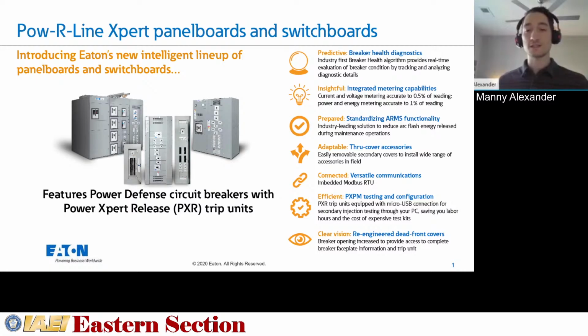All of the data that these breakers are collecting is incredible and great, but we want to be able to provide that data to a higher level system for action to be taken. Other things such as the ability to plug your computer via micro USB port into the trip unit gives you the ability to perform secondary injection testing on the breaker, pull all of that great breaker data, and perform test reports that can be compiled in PDF format. So just a lot of great things that you can pull from these breakers used in our panelboards and switchboards.